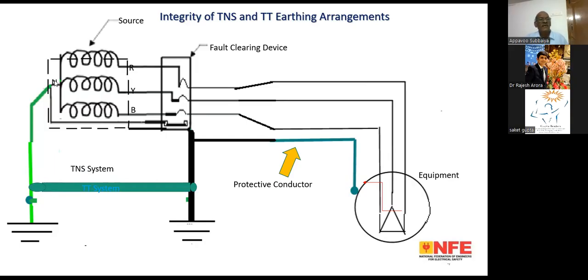In the TN-S system, the source neutral is connected to earth, and your equipment frame will be brought up to the main terminal. Then it will be connected to earth. Of course, you will have another earth electrode for your installation also, and that is required for lightning protection and other things. Otherwise, this is the only thing. Here you can see if any fault occurs, everything will go through the earth conductor, the PE conductor. This we call the PE conductor. This will flow and it will reach the source.